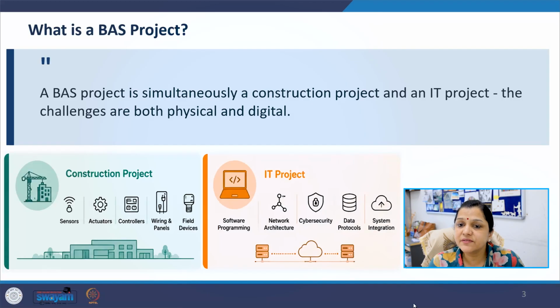For example, even if the software is excellent, poor sensor installation can destroy system performance. Similarly, perfect hardware installation is not enough if the control logic or network integration is poorly designed. Therefore, successful building automation system implementation requires coordination between architects, mechanical engineers, electrical engineers, IT professionals, and facility managers.